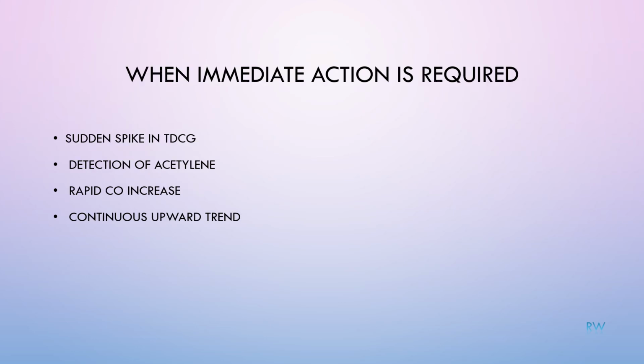Immediate investigation is required when there is a sudden spike in total gas, detection of acetylene, rapid increase of carbon monoxide, or continuous upward trend over multiple tests. Such cases require engineering evaluation and possible outage planning.